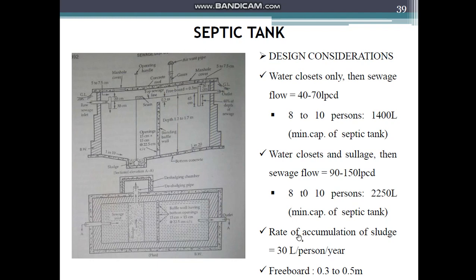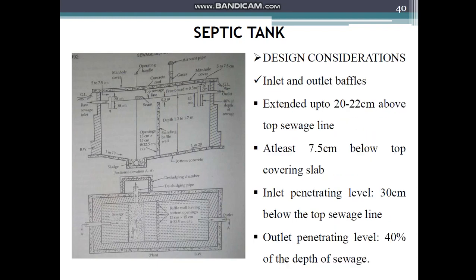The rate of accumulation of sludge is 30 liters per person per year, which is very useful in deciding the volume of sludge deposited. Freeboard in the tank is usually around 0.3 to 0.5 meters.